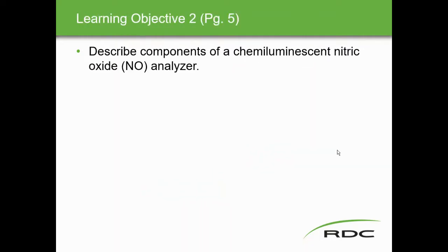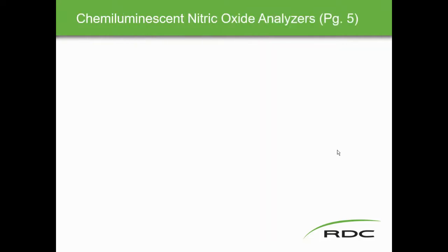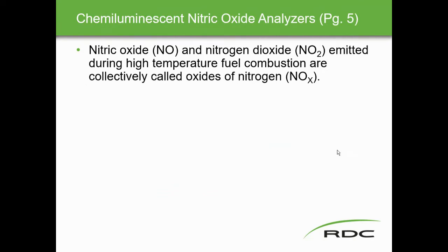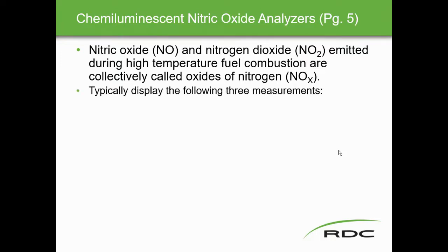Learning objective two: describe components of the chemiluminescent nitric oxide analyzer. Nitric oxide and nitrogen dioxide are emitted during high-temperature fuel combustion — that's what comes out of your plant stacks. Collectively called NOx, these oxides of nitrogen are the combination of NO and NO2. The analyzer typically displays three measurements: NO, NO2, and NOx.